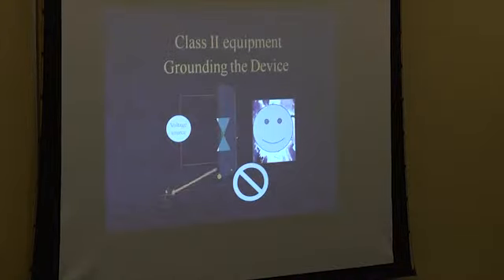Why this doesn't work in the operating room is that this ground wire either gets tripped or something happens to it, such as an anesthesia machine rolling over the wire and breaking it off. So the problem is you can't be sure it's going to work.